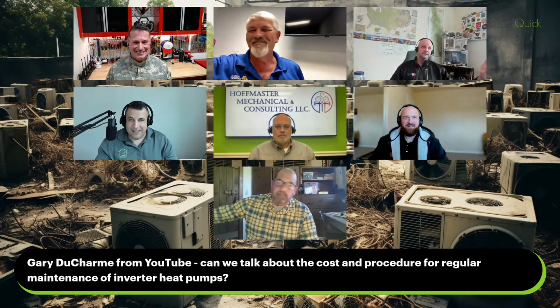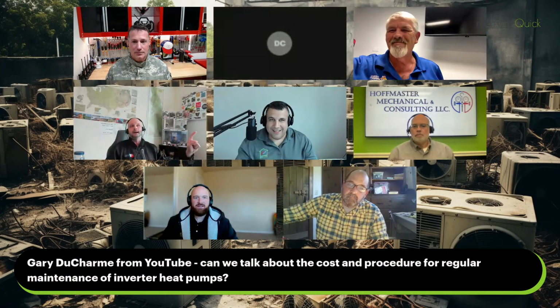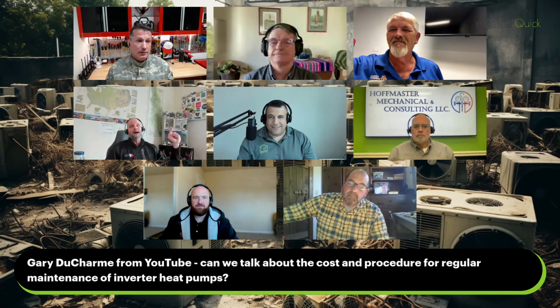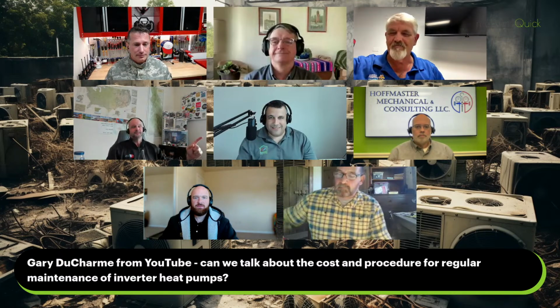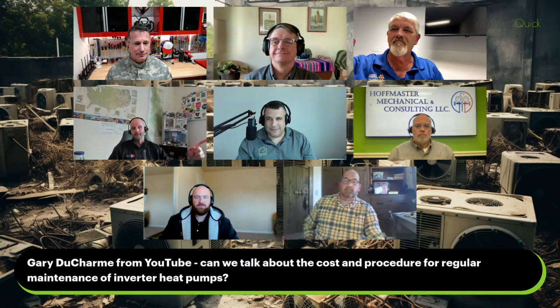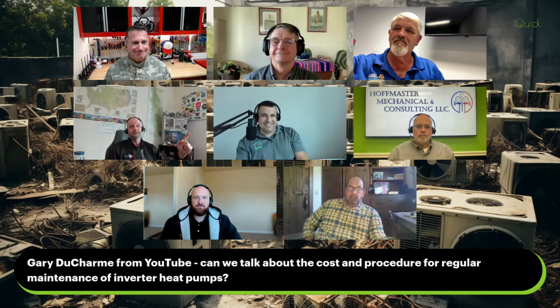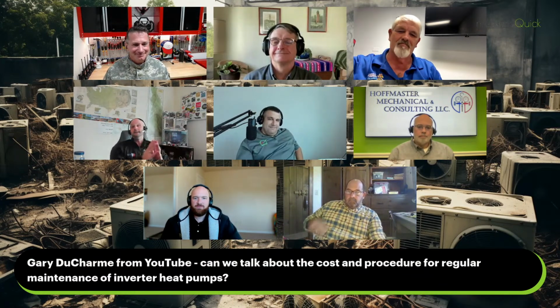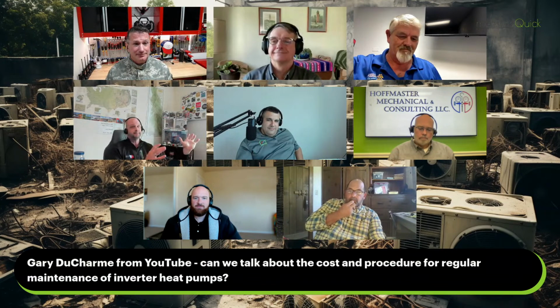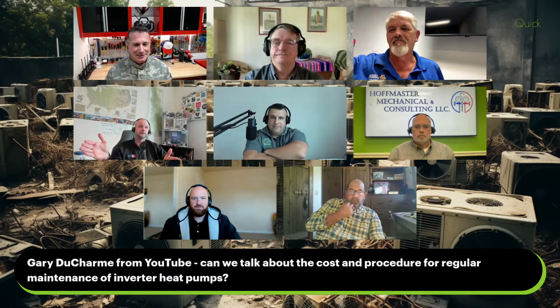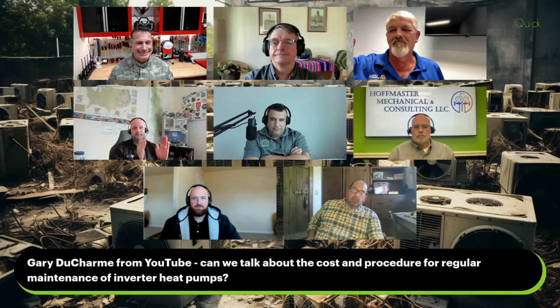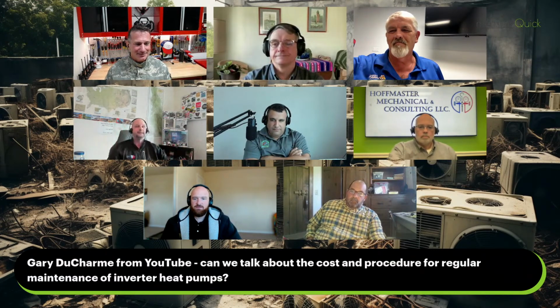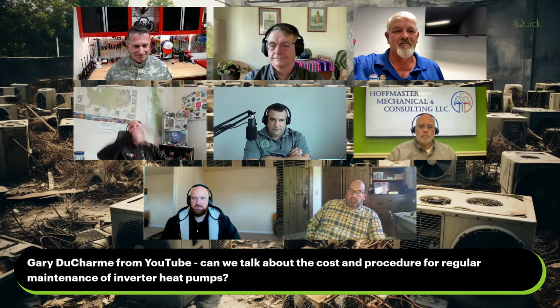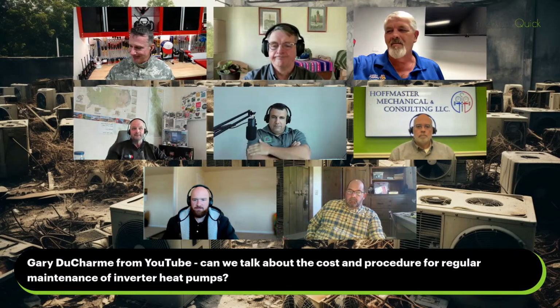One important point—one of the biggest maintenance savers on heat pumps is contractor education, believe it or not. I have guys go back five times to fix stuff that doesn't need fixing because they installed it wrong—all they had to do was understand the thing they were installing. Then they charge the customer, the customer gets upset and blames the heat pump, but it's not the heat pump, and it's not necessarily the contractor—it's the shop that didn't teach him what he was installing in the first place. That's a huge point I want to make to our contractors out there.